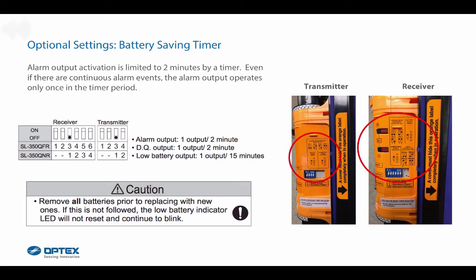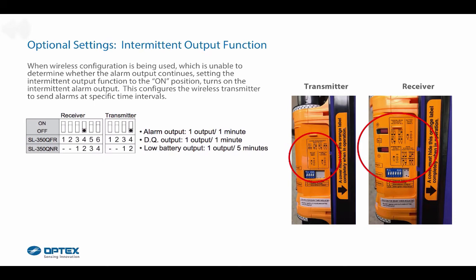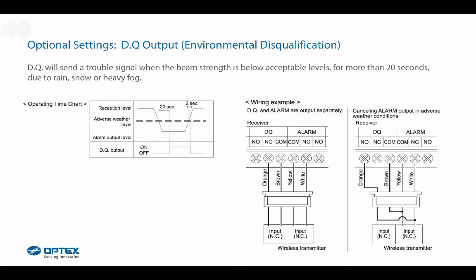Caution: remove all batteries prior to replacing new ones. If this is not followed, the low battery indicator LED will not reset and will continue to blink. For the optional intermittent output function: when wireless configuration is being used and it is unable to determine whether the alarm output continues, setting the intermittent output function to on turns on intermittent alarm output, configuring the wireless transmitter to send alarms at specific time intervals. The optional DQ output environmental disqualification sends a trouble signal when the beam strength is below acceptable levels for more than 20 seconds due to rain, snow, or heavy fog.